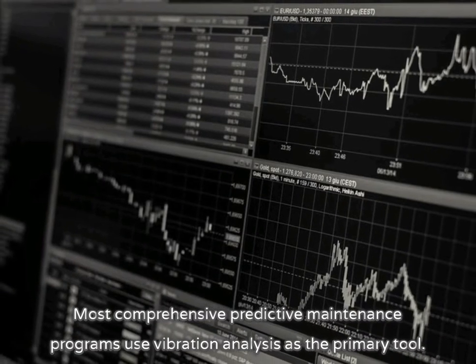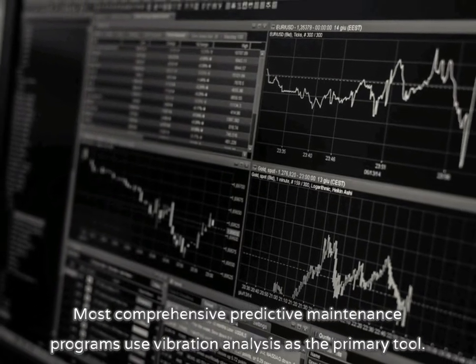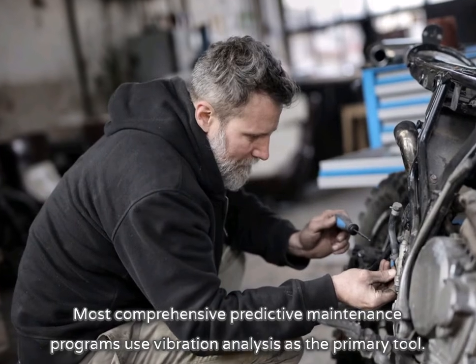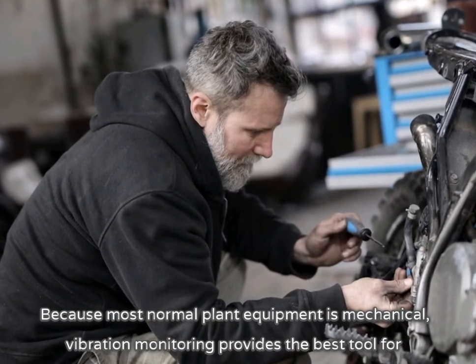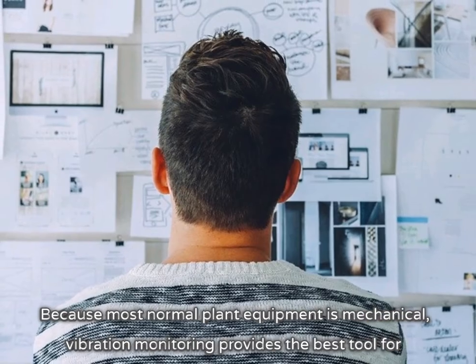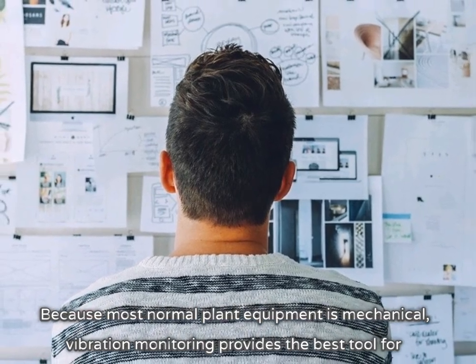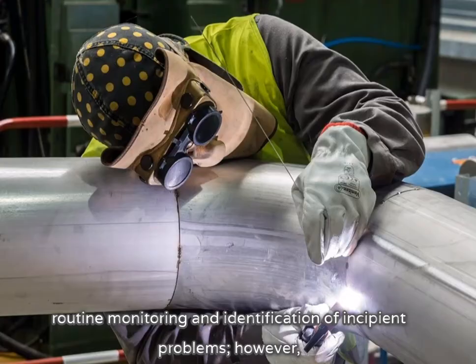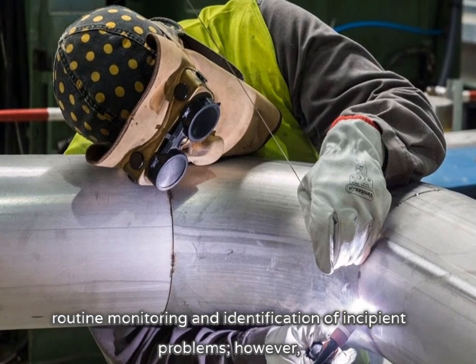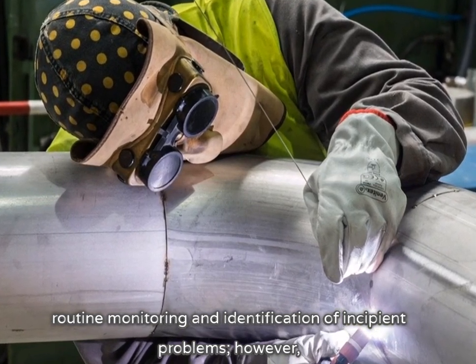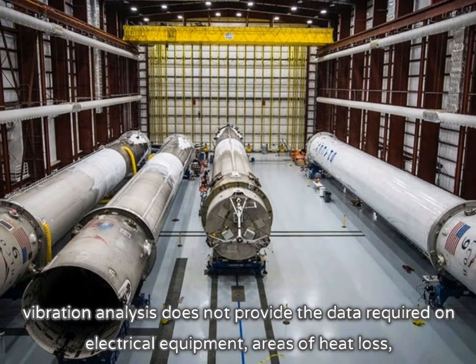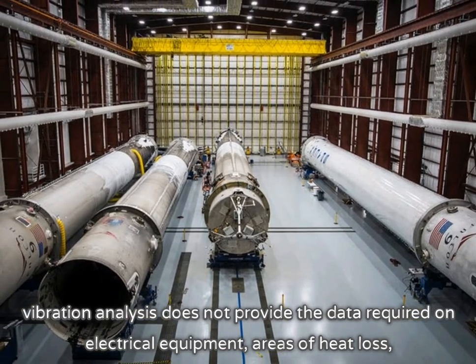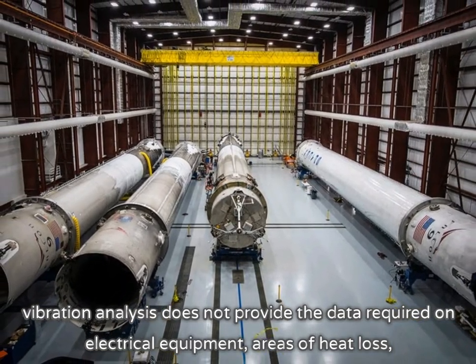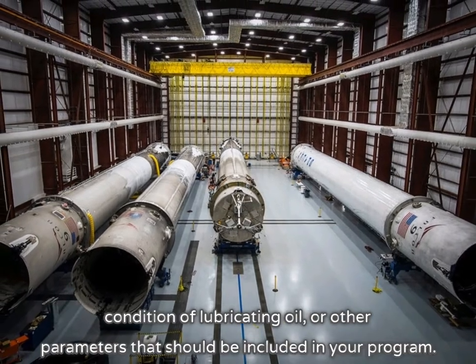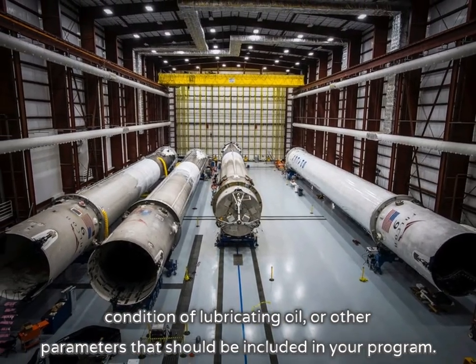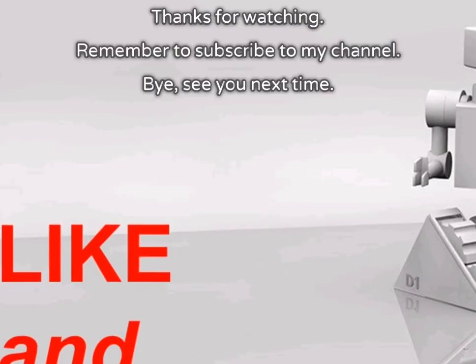Most comprehensive predictive maintenance programs use vibration analysis as the primary tool. Because most normal plant equipment is mechanical, vibration monitoring provides the best tool for routine monitoring and identification of incipient problems. However, vibration analysis does not provide the data required on electrical equipment, areas of heat loss, condition of lubricating oil, or other parameters that should be included in your program.